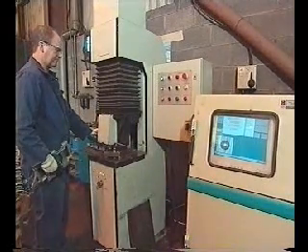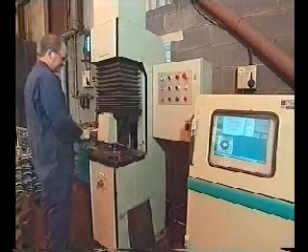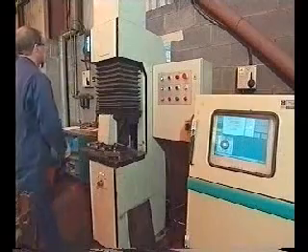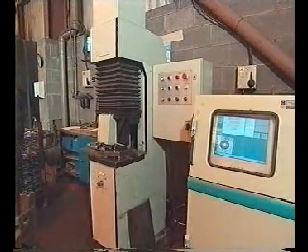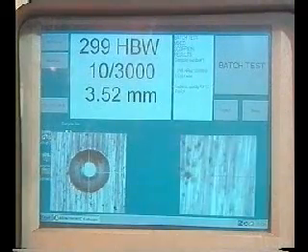The machine makes the test cycle automatically. In the final part of the test cycle, the Bruntronic microscope measures the diameter of the indentation automatically within one second. It displays the Brinell hardness test result and the diameter of the indentation in black if the test result is within tolerance, and in red if it is not.